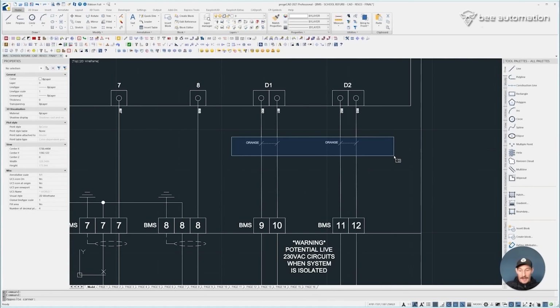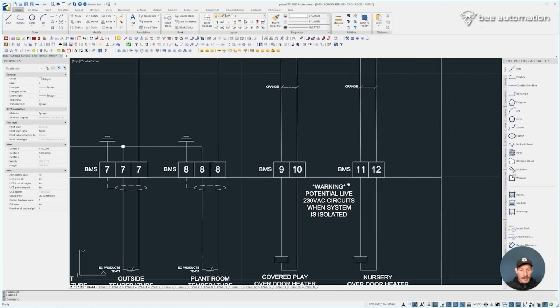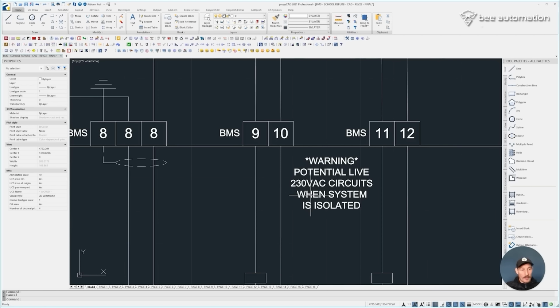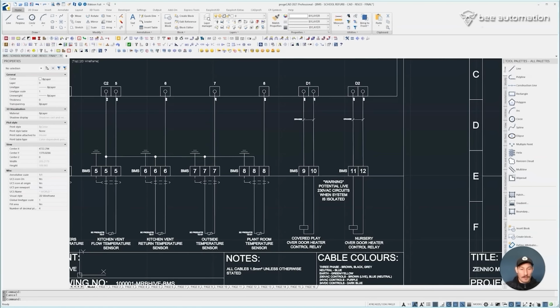I also need to remember when I do my labeling to add a warning label indicating that these terminal blocks and circuits are potentially 230 volt AC live even when the main isolator is off and the panel is isolated, because these could still be feeding 230 volt AC into the panel. That's the indicators or modifications showing these cables are orange, and I've put that label in there, which I'll also stick within the panel by these terminal blocks.